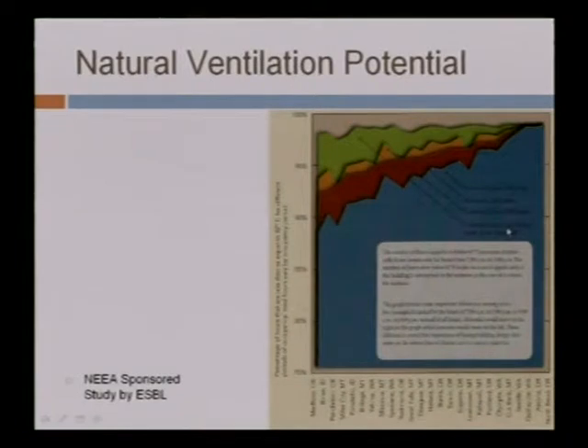excluding June 15th to September 15th, which is the normal operation for schools, we immediately have 97% of the time where the temperature is less than 82 degrees Fahrenheit. This is a very important cutoff criteria where we can expect free cooling from natural ventilation. This chart suggests that our schools, if properly designed, don't need cooling, or at least not as much cooling as we have now.